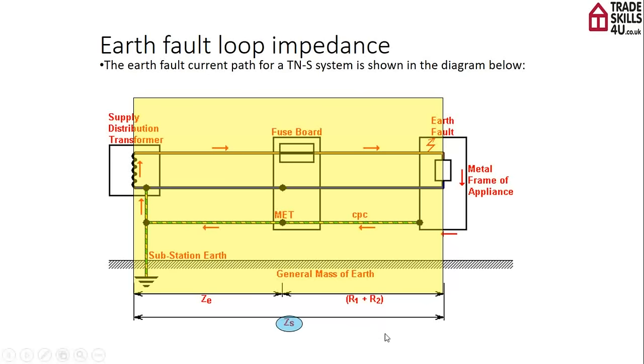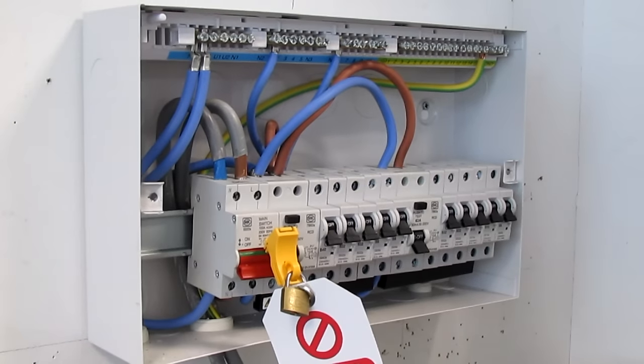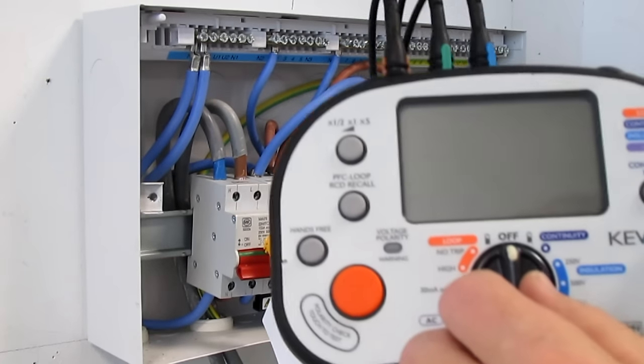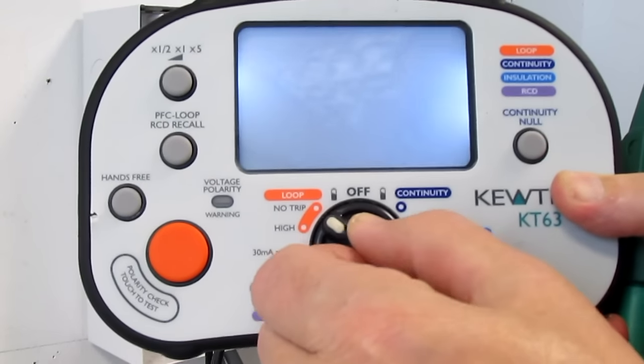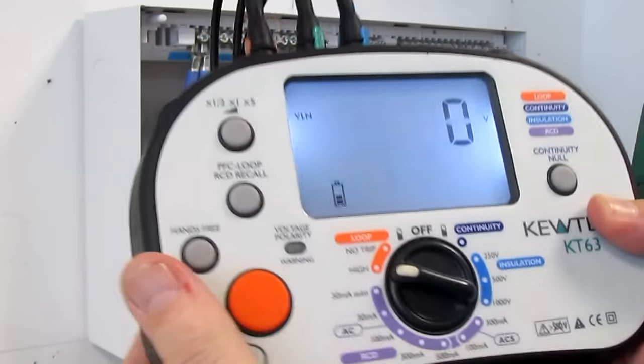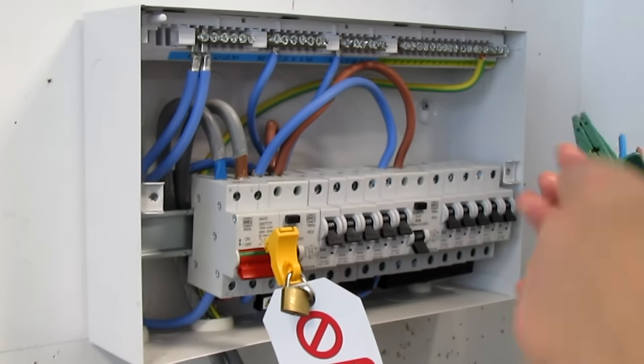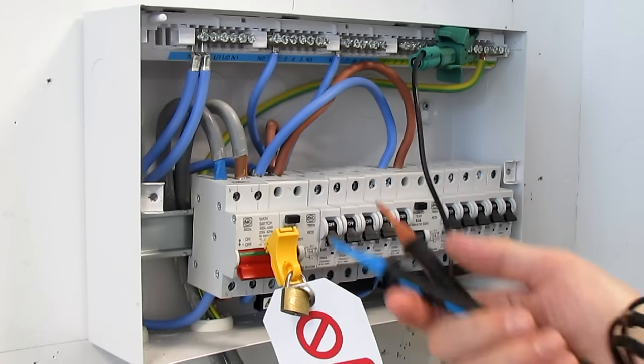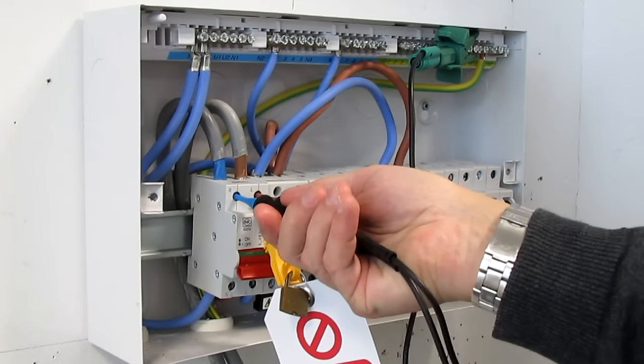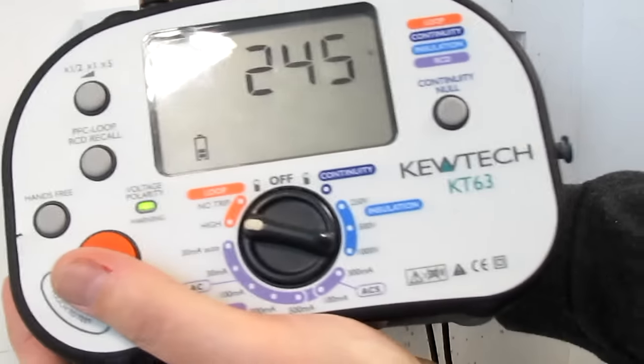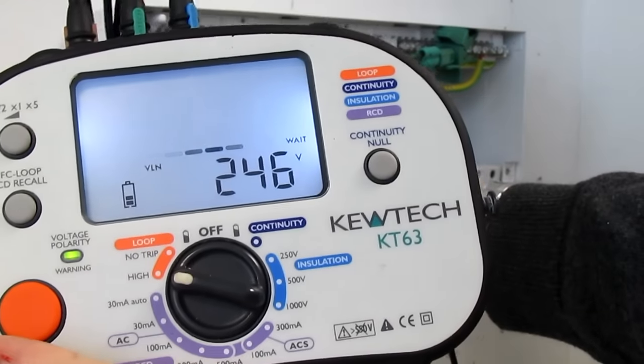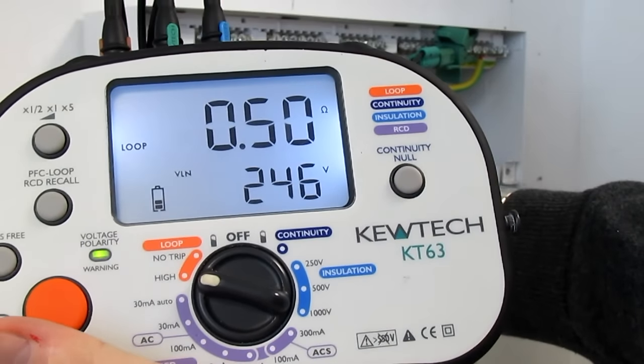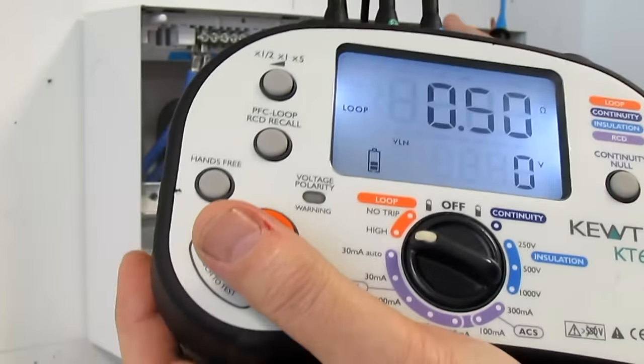On our schedule of test results in the top left-hand corner, you will see ZS at dB. I have to do a ZS at dB at the installation origin as well. So set my meter to high — this time the earthing conductor stays connected. Because there are no parallel paths here, I'm expecting to get the same reading, and in a domestic situation it would probably be the same. And there we go — 0.50 ohms. ZS at dB.